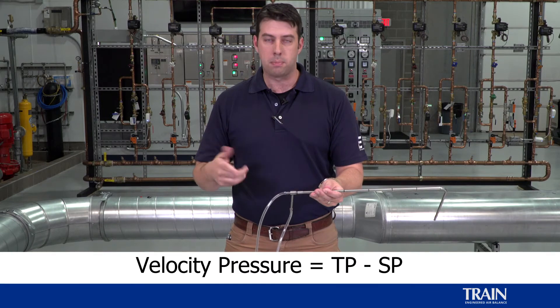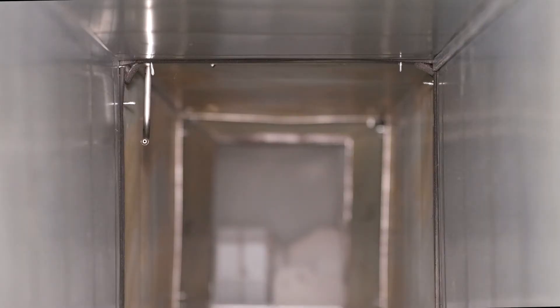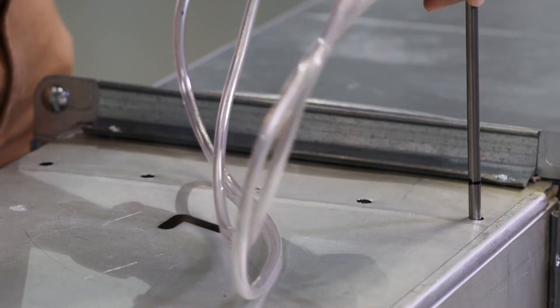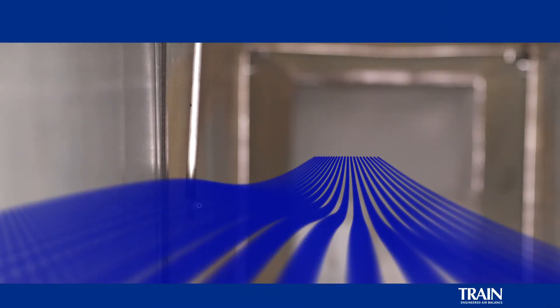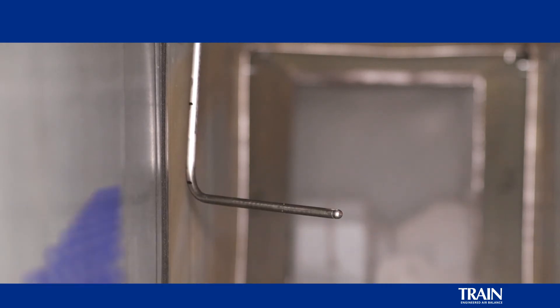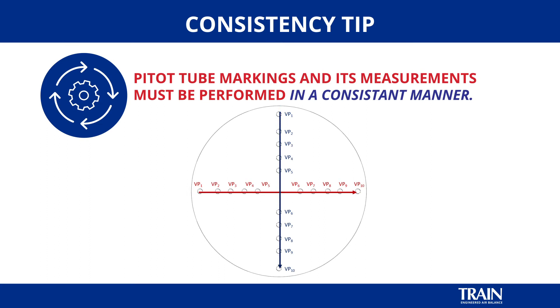The velocity pressure is the total pressure minus the static pressure. We can visually demonstrate the location of the pitot tube inside a duct when performing a pitot tube traverse. The pitot tube must be oriented into the airstream and perpendicular to the airstream in a cross-sectional plane. We do not want to see the pitot tube at an incorrect angle, since that will produce erroneous readings and provide unacceptable data. It is also important that the pitot tube be gridded off and measurements taken in a consistent manner.